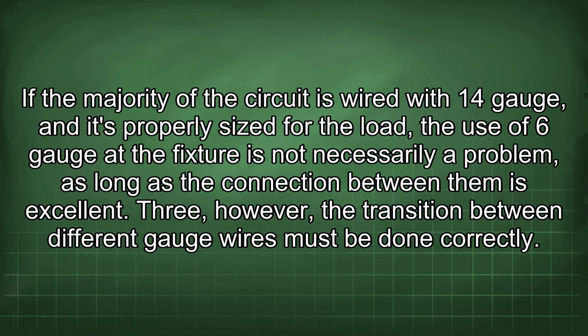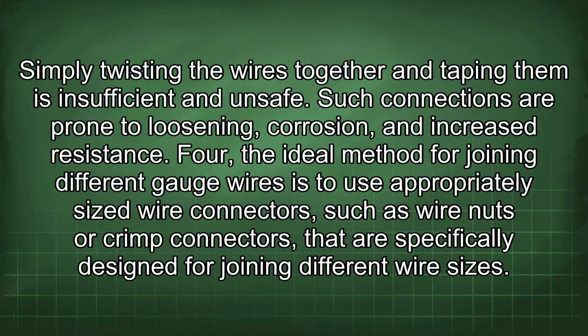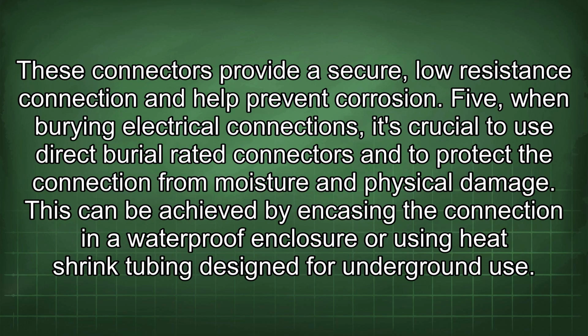3. However, the transition between different gauge wires must be done correctly. Simply twisting the wires together and taping them is insufficient and unsafe. Such connections are prone to loosening, corrosion, and increased resistance. 4. The ideal method for joining different gauge wires is to use appropriately sized wire connectors, such as wire nuts or crimp connectors, that are specifically designed for joining different wire sizes. These connectors provide a secure, low-resistance connection and help prevent corrosion.